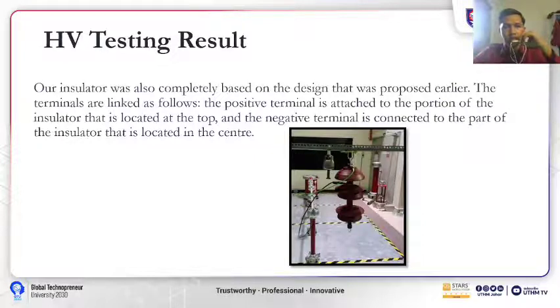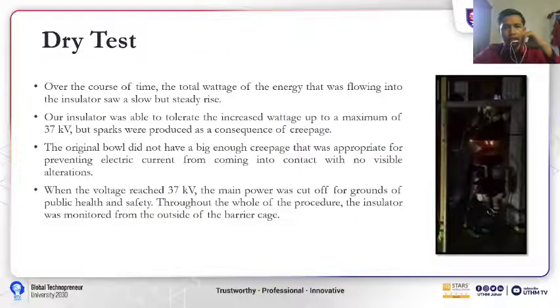The terminals are linked as follows. The positive terminal is attached to the portion of the insulator that is located at the top, and the negative terminal is connected to the part of the insulator that is located in the center. And for the dry test, over a course of time, the total wattage of the energy that was flowing into the insulator saw a slow but steady rise.